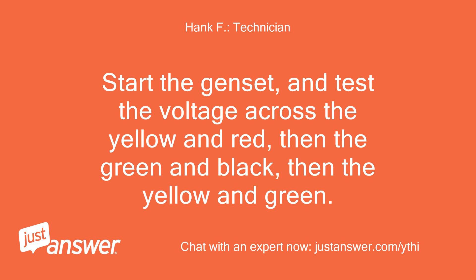At that terminal block, remove the wires that lead to the receptacles at the control panel, leave the ones coming from the stator attached. Start the genset, and test the voltage across the yellow and red, then the green and black, then the yellow and green. What voltages do you see here?